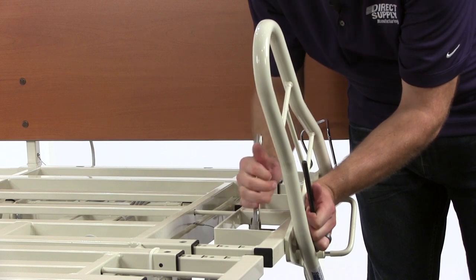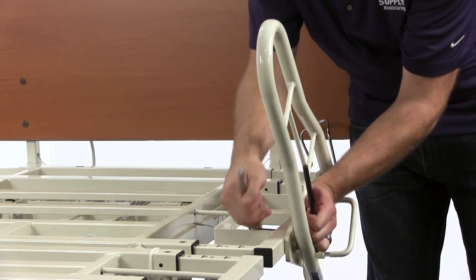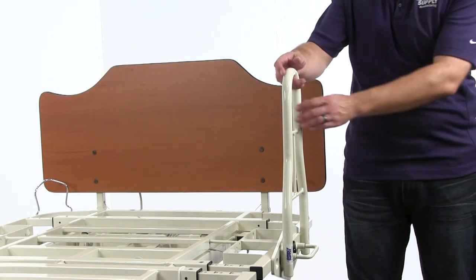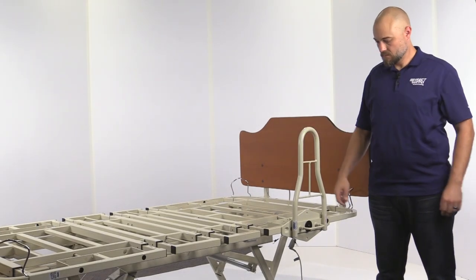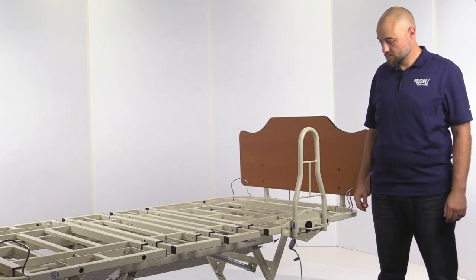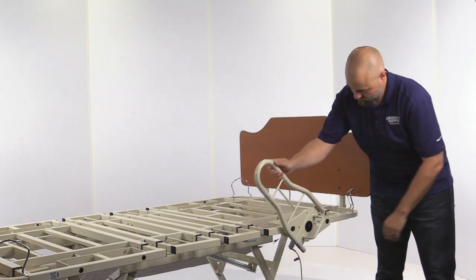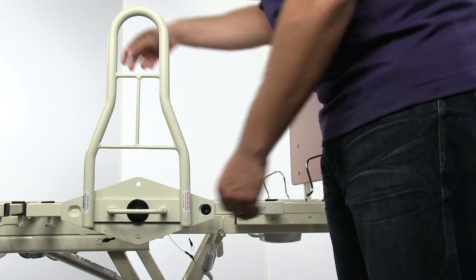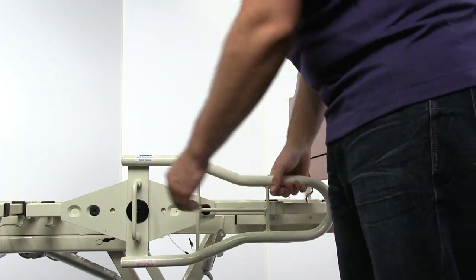Before putting the assist device into use, review the installation and overall bed system for functionality and safety. The assist device should feel solid and stable. Ensure that 50 pounds of force can be exerted on the assist in any direction without damage or permanent deflection. Verify that the device can pivot to the desired directions and that the pivot lock system is preventing pivoting in other directions.